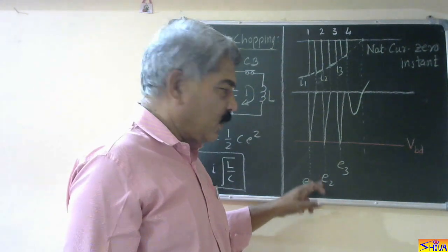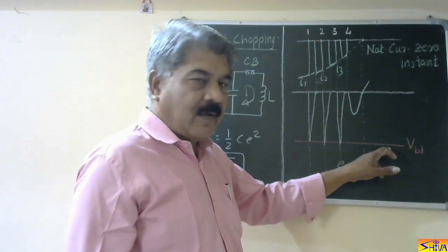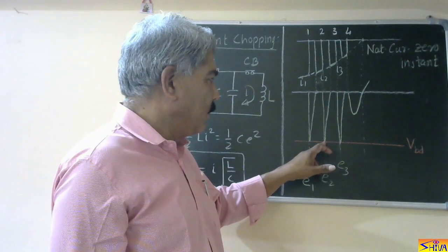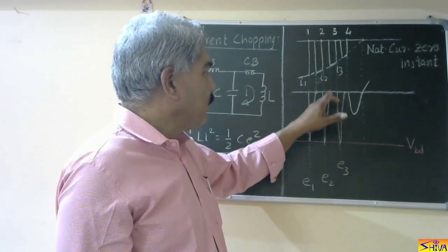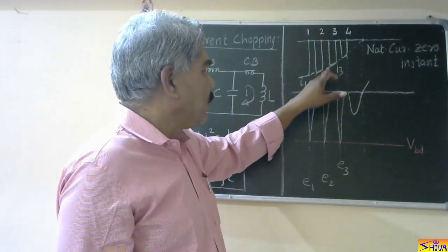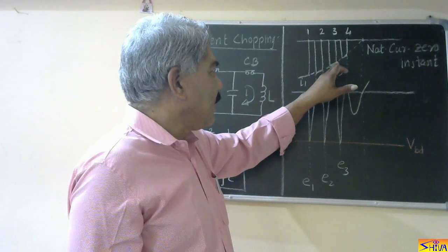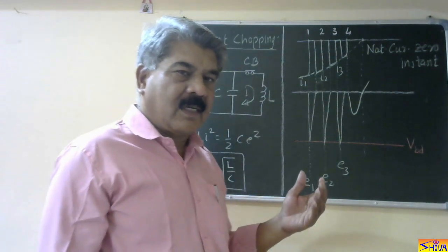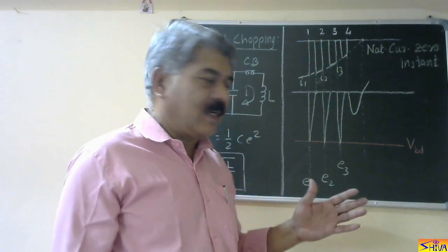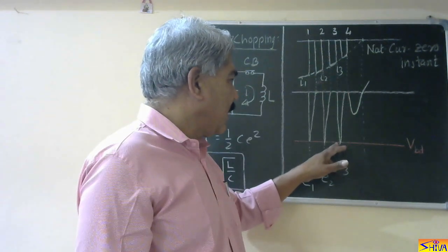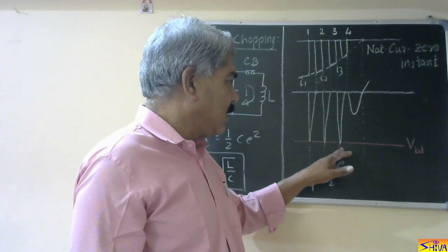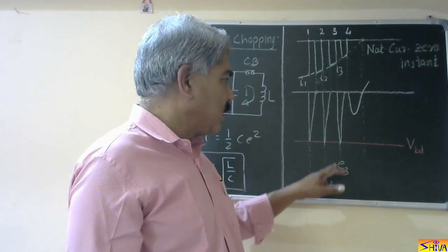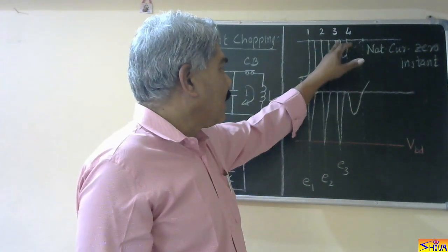Now let us assume this voltage is also more than the voltage required to strike the arc. So at this instant, as soon as this prospective voltage is attaining this value, the arc strikes and voltage becomes zero. So when voltage becomes zero, current starts flowing. So again, current starts flowing, and at this point, let us say third current zero instant occurs, because this current is not sufficient to maintain the arc. So again, same phenomena will repeat, and if this voltage is sufficient to strike the arc, then again at this point, that is corresponding to prospective voltage E3, arc will strike, current will start flowing.